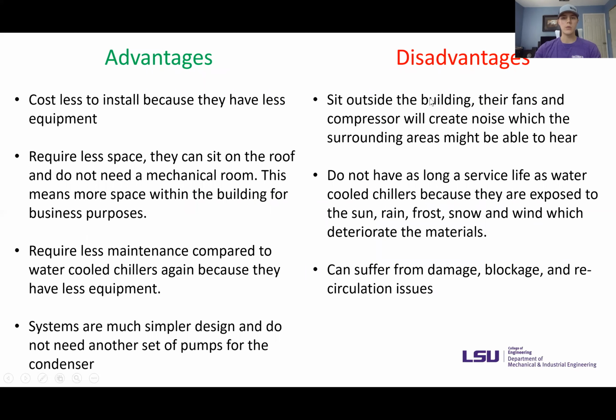So the advantages for choosing an air-cooled screw compressor would be that they cost less to install because they have fewer parts compared to a water-cooled chiller. They require less space because they can sit on top of the roof and don't need a mechanical room compared to a water-cooled. This means more space within the building for business purposes. They also require less maintenance because they have fewer parts. And the systems are much simpler to design and don't need another set of pumps for the condenser, which would be the water cooled. The water cooled needs an extra set of pumps.